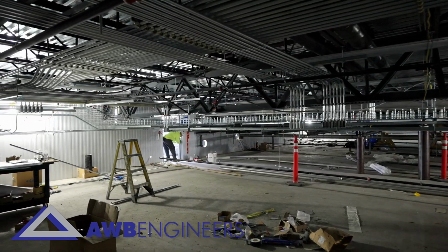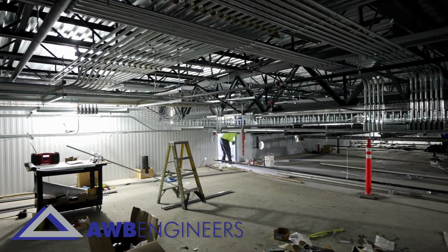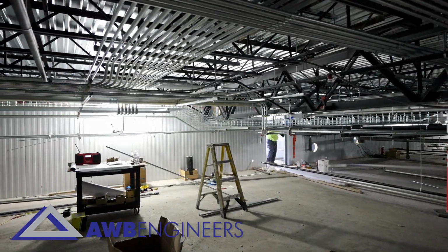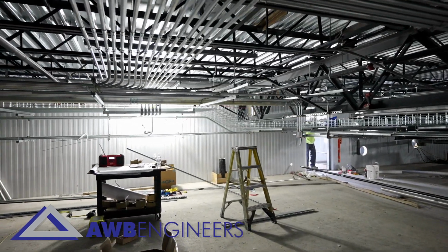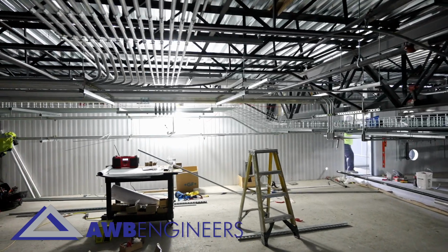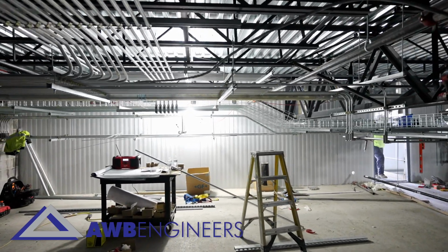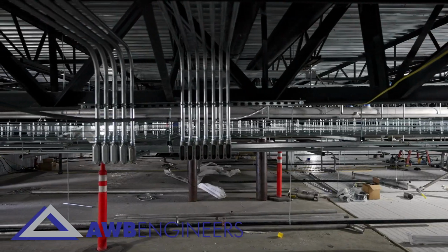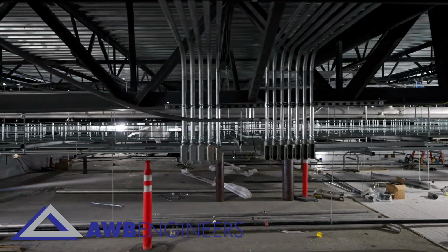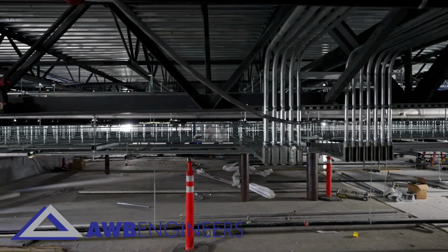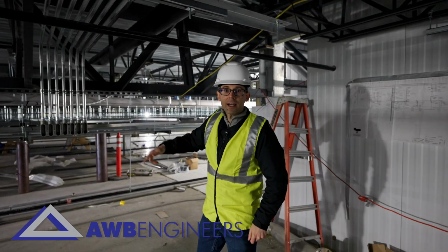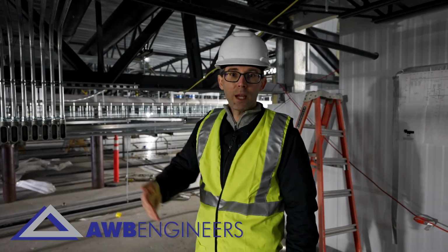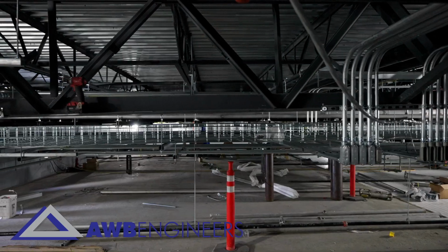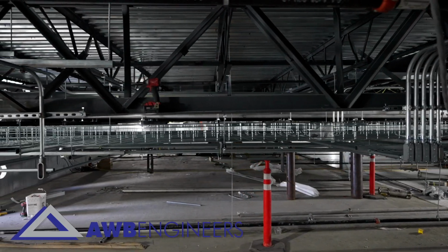We're inside the interstitial space and here we can see all of the conduits with wiring in them that are coming from the electrical rooms and are routed to the cable tray. The wire located inside the conduits will come into the cable tray and then will be switched to tray cable and it will be routed throughout the facility on that cable tray.